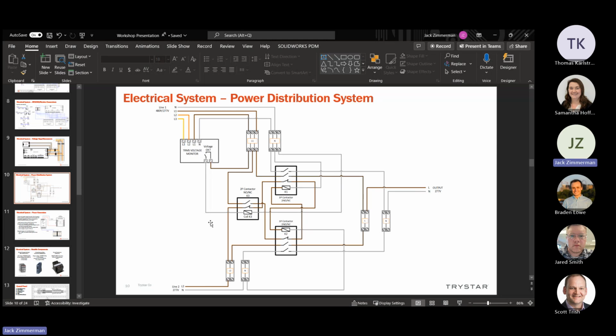But I will say this system is kind of set up for a utility and a generator, but it would work with two generators. And so again, because I'm the most ignorant, why would I favor one generator? Because a lot of times, even in a system that has two generators where you're resting one and doing the other, you will have a bigger main generator and then a backup. So some generator systems are what I described, where you switch between them equally, but a lot of the time it is a main generator, assuming that the generators are not equal. Yes, and remember, there's a main one and a smaller one or backup or whatever.